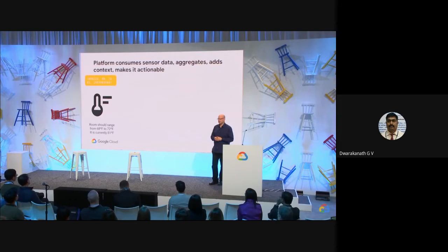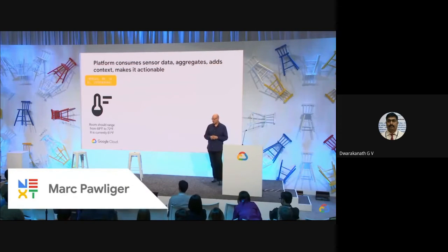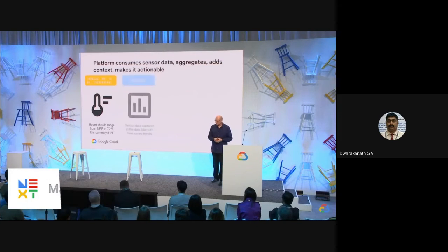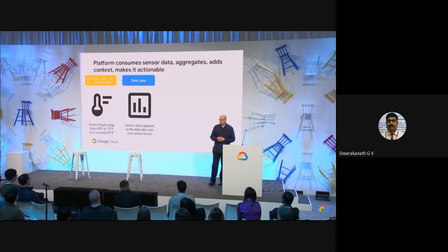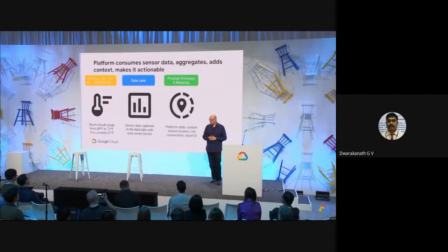A particular problem you might face is an out-of-set-point temperature. Look at the box in yellow—that's what the data looks like raw coming from the device. It says this sensor should be in the range of 62 to 72 Fahrenheit, but it's currently 81 degrees, so obviously that's problematic. This lands in the data lake—the sensor captured the data, put it in there, and tagged it with a timestamp. None of this is unusual if you've dealt with a typical building automation system before.